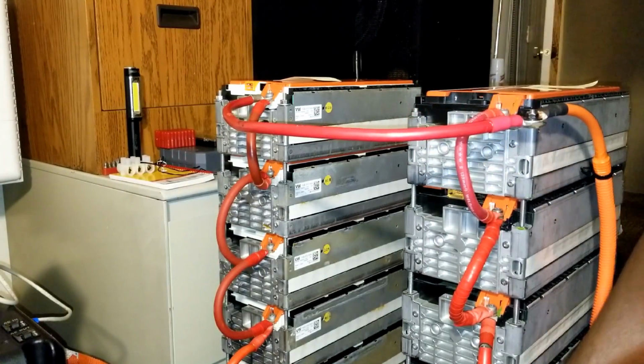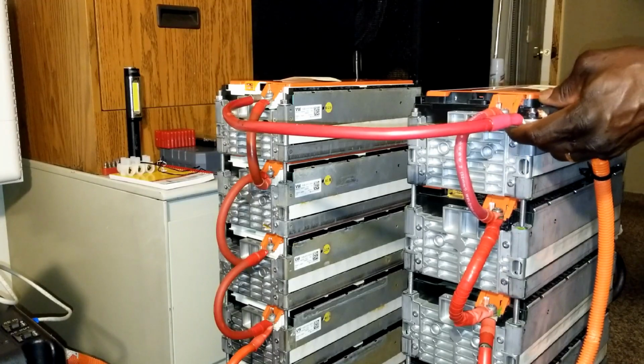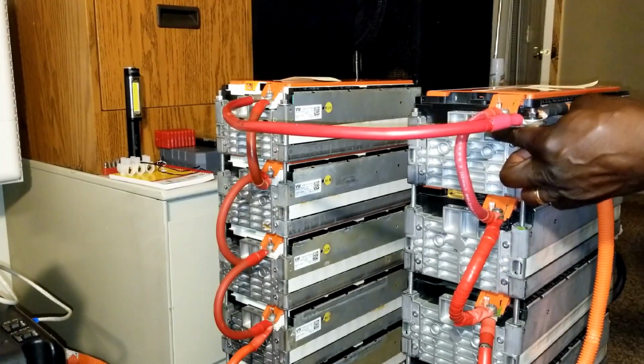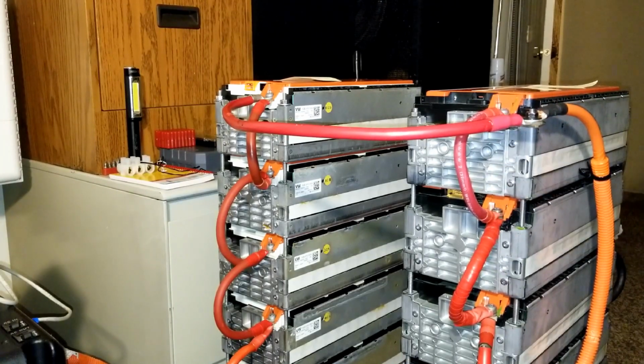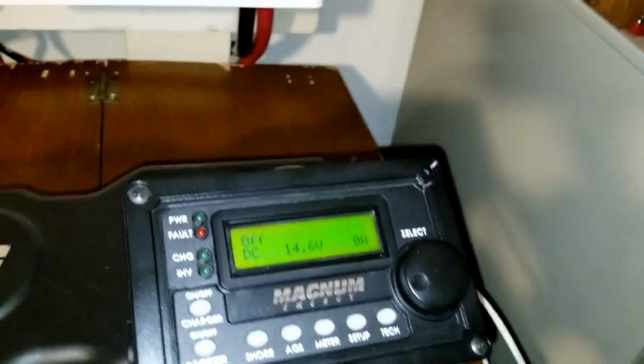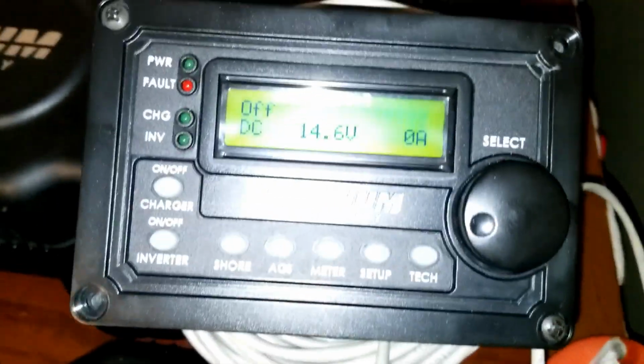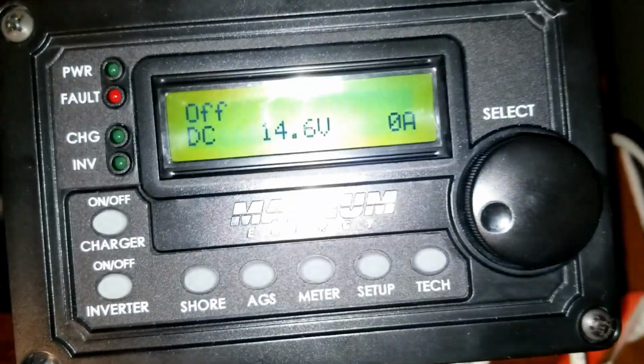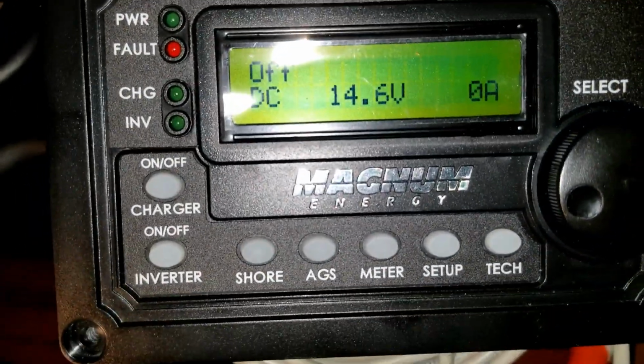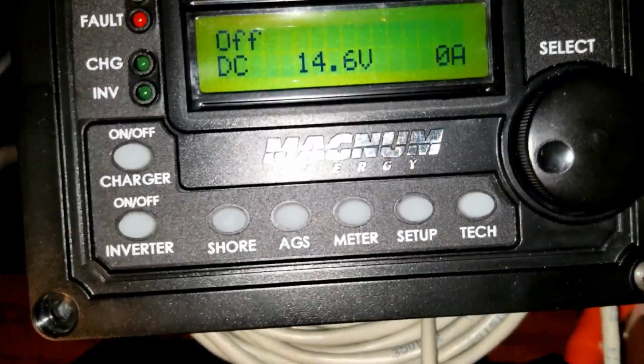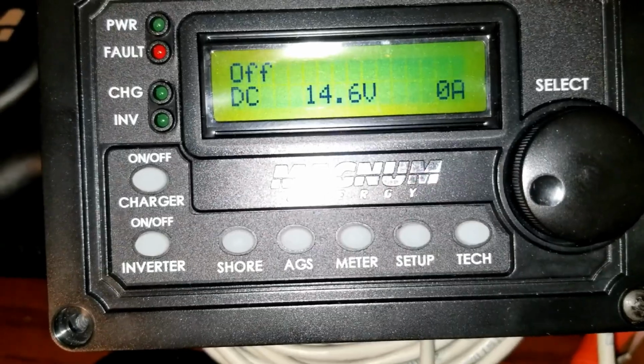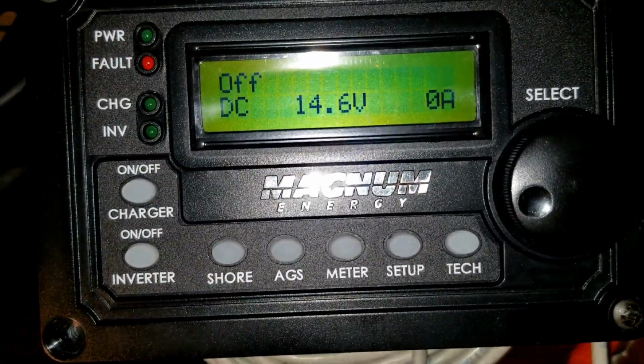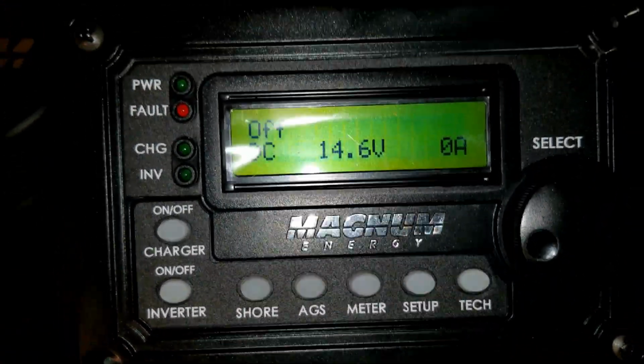Okay, so we got this guy here pretty much, and we are done here. So let's check this out. The voltage we had earlier, 14.51. The inverter is reading 14.6. So we might probably need a calibration on this.